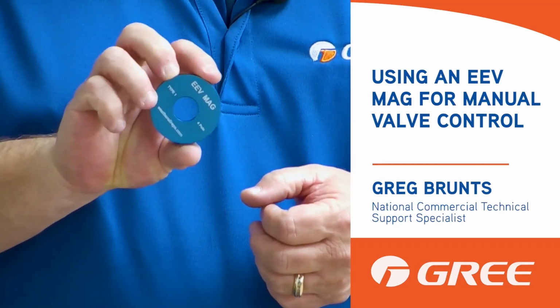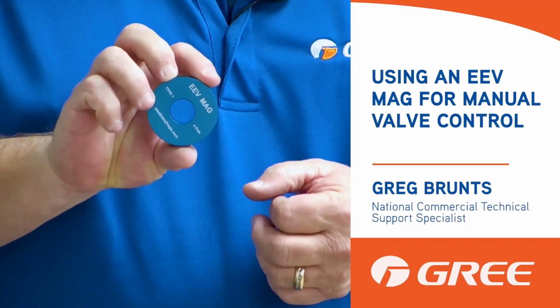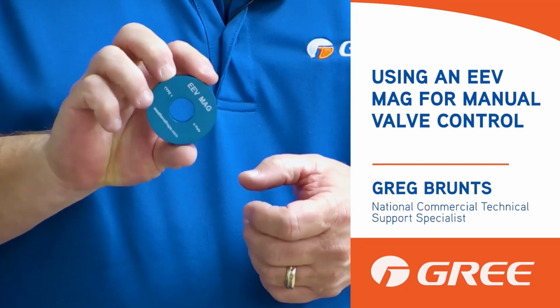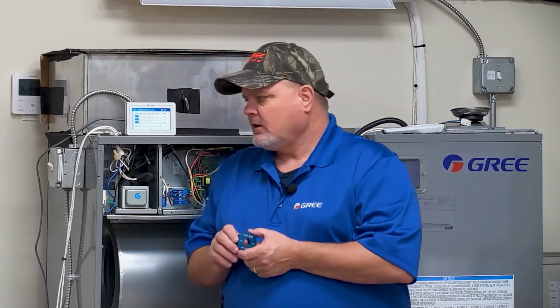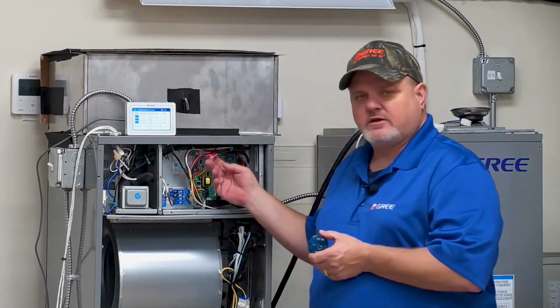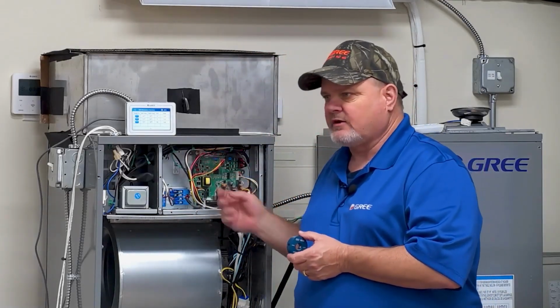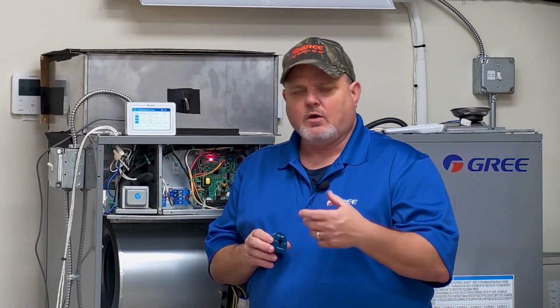Hi, GREE here. I thought I'd show you something I was just messing around with down here in our lab in Atlanta. I have one of these EEV mags. This is actually a type 1. It fits our EEV bodies perfect. So I just want to show you how you can use this EEV mag to manually open or close your EEV and actually do your refrigerant flow. In order to do that, what I did was I disconnected the power cable going to the EEV, because when I pull that power head off, I don't want to put power to the EEV without it being on the valve body of the EEV.